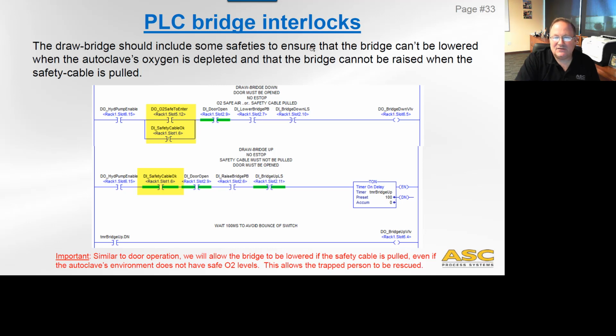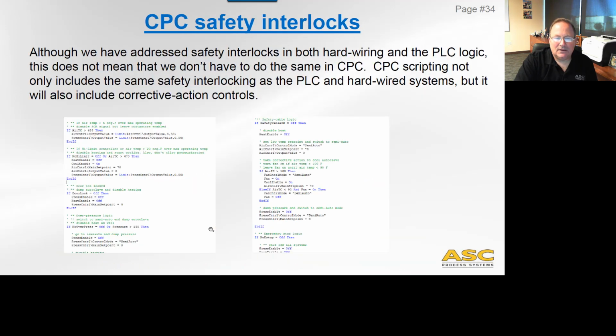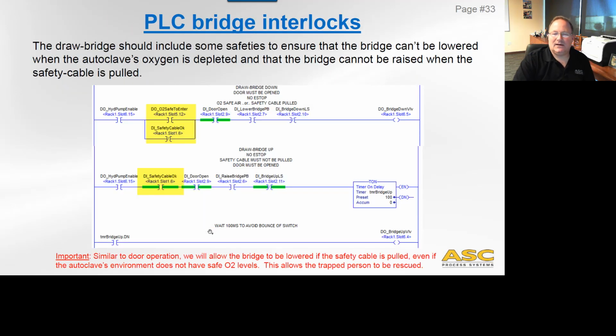The drawbridge should include some safeties to ensure the bridge can't be lowered when the autoclave oxygen is depleted, and the bridge cannot be raised when the safety cable is pulled. So you're going to see these two permissives are new, kind of similar to the door operation. We allow the bridge to be lowered. So here we're allowing the bridge to be lowered if O2 is safe or if the safety cable is pulled, right? And so this allows us to get someone out of that autoclave quickly, even if the autoclave has unsafe oxygen. And we're not going to raise the bridge if someone has pulled the safety cable. Obviously, that's locking them in the autoclave, right? So that basically is all of your PLC interlocks.